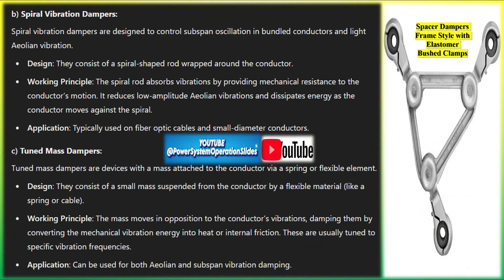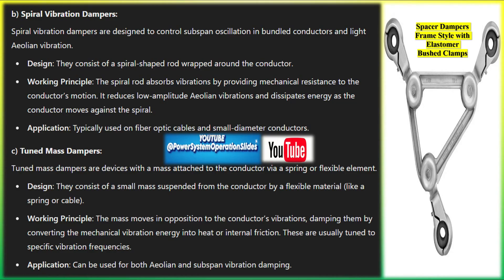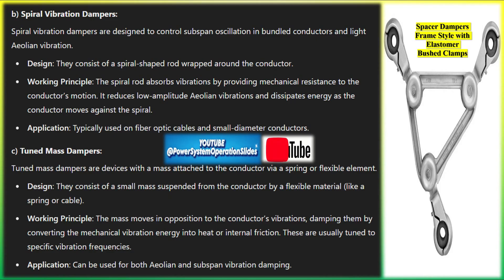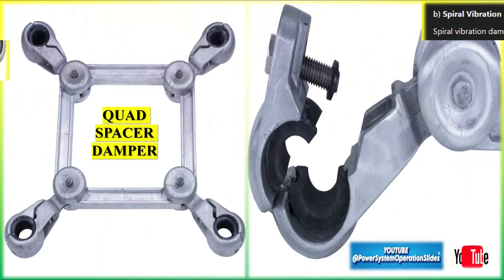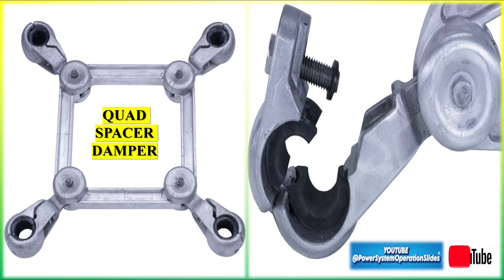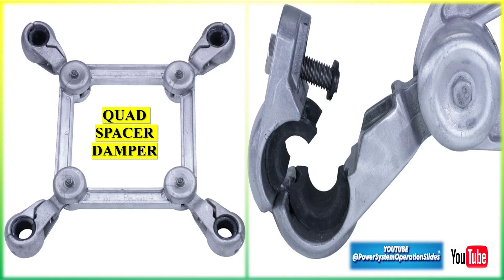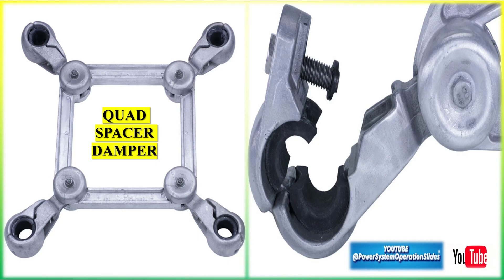Spiral vibration dampers are designed to control subspan oscillation in bundled conductors and light Aeolian vibration. They consist of a spiral-shaped rod wrapped around the conductor. The spiral rod absorbs vibrations by providing mechanical resistance to the conductor's motion, reducing low-amplitude Aeolian vibrations and dissipating energy as the conductor moves against the spiral. They are typically used on fiber-optic cables and small-diameter conductors.